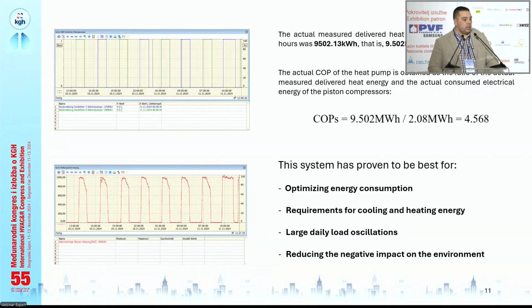And the last diagram for us was the most important, and this is the measuring of the heat energy that was actually delivered to the buffer tank and the heating system. From this diagram, we can see that the actual measured heat energy that was delivered to the buffer tank was 9.5 megawatt hours in the period of 24 hours. And since in the previous diagram we saw the actual electrical consumption that was already measured, we were able to calculate this realistic COP that was produced.